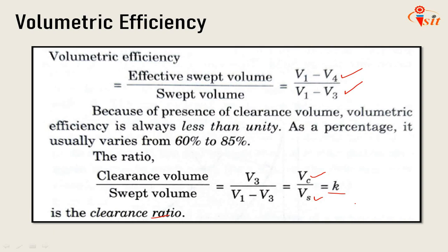The greater the pressure ratio through the reciprocating compressor, the greater will be the effect of the clearance volume, since the clearance air will now expand through a greater volume before intake conditions are reached.